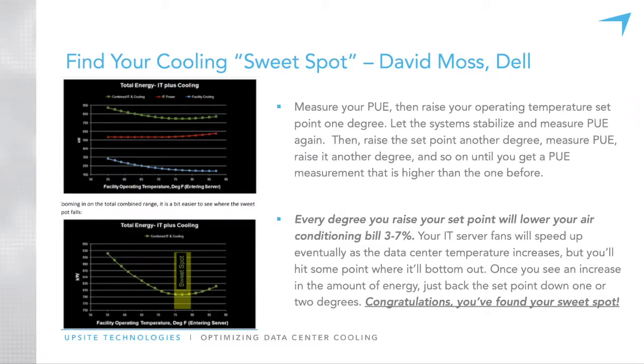As every day, week, month, and year went by, all the data I gathered ended up proving that claim correct. So if you're measuring your PUE, and you know the kilowatt hours used for IT equipment versus mechanical equipment, you can start to quantify how a 3 to 7% savings over a week, month, or year adds up to something very significant.